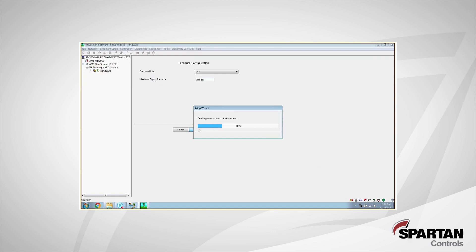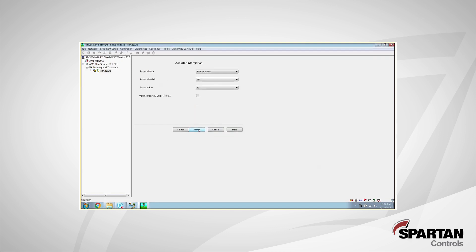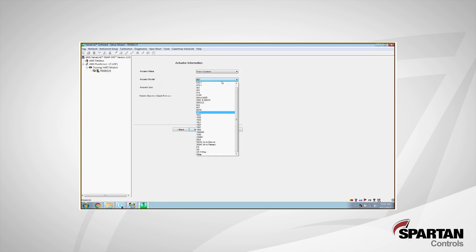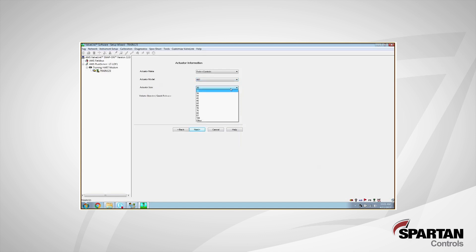Next, it's going to ask us what type of actuator we're actually setting our DVC up on. In my case, looking at the actuator nameplate, I have a Fisher Controls, a 667 size 30. But you'll see under these headings that there's many different options to choose from depending on what type of actuator you have, as well as many different sizes. The DVC uses this information to choose a tuning set to start out on, as well as whether or not you have a volume booster or quick exhaust in your assembly. So I'm going to click next here.